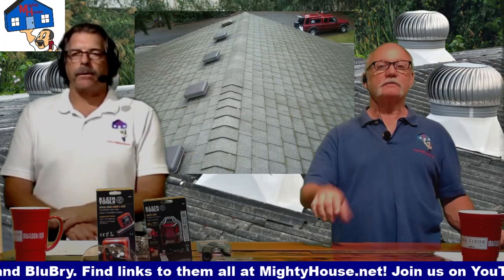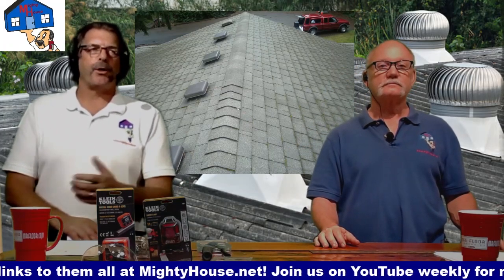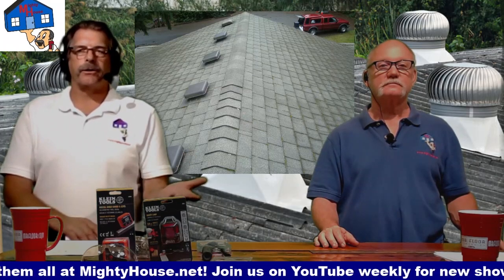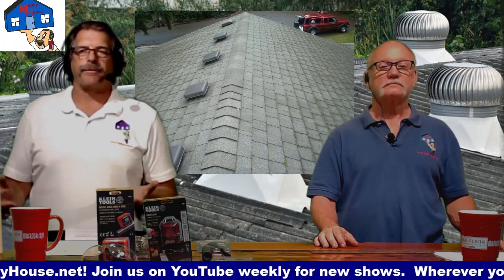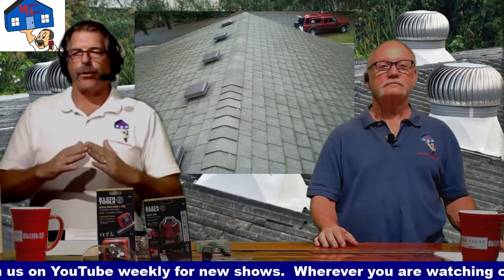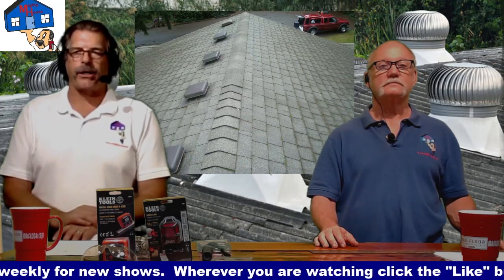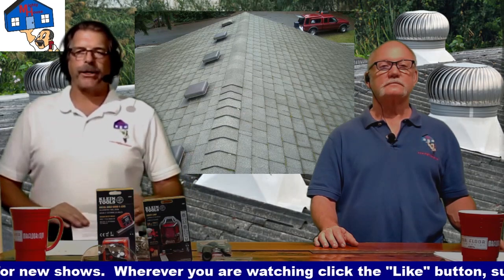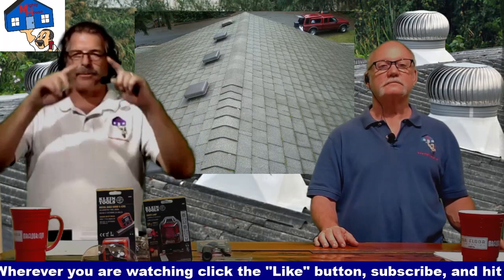Well, the insulation, the thickness of it. But for a typical attic, whether it was a 1,500 square foot ranch or a two-story that was 3,000 square feet, where the second floor is 1,500 square feet, and regardless of the pitch of the roof, yes, you have more cubic air to move. But what we're trying to do is figure out how much area of venting you need so that you can get a convection current going from your soffits up through the roof.